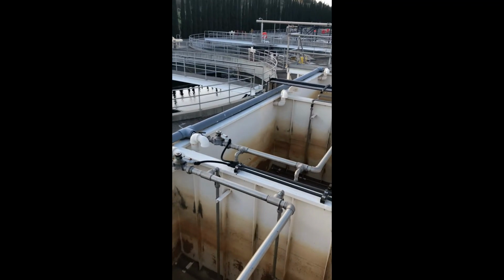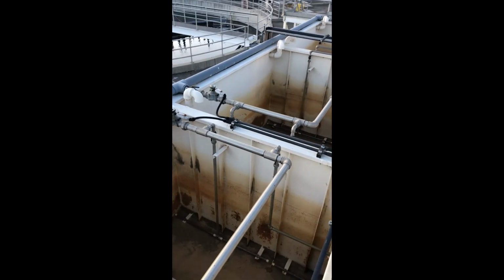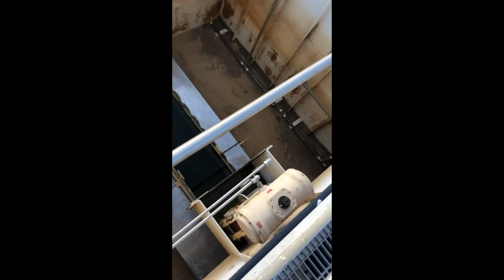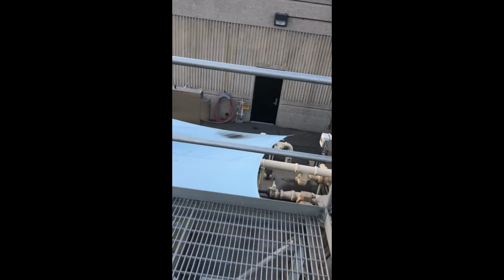On this filter system, all the valves, none of them are modulating. They're all open and close. So it's a good application for pneumatics. But anyhow, that's what they put on it. So that's the top side of the filters. Level sensor. Our filters have an HMI, so you can kind of take a look at the system, see what's going on.